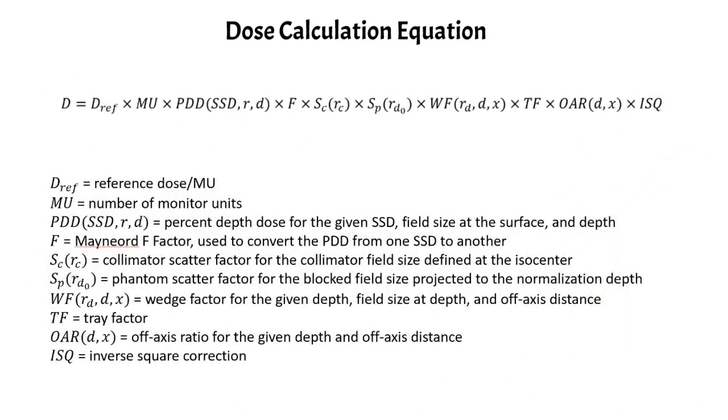So here's what all of the different terms mean. We have DREF, which is your reference dose per monitor unit, which is established during your TG51 calibration. MU is just your number of monitor units. PDD, which is a function of SSD, r, and d, is the percent depth dose for the given SSD for the field size at the surface and whatever depth you're calculating at.